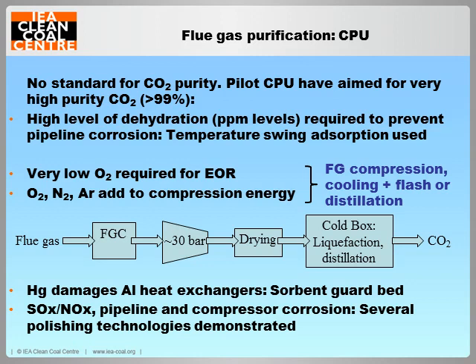Even though oxy-fuel flue gases are enriched in CO2, contamination due to air ingress, residual oxygen and conventional flue gas contaminants means that a fairly elaborate purification process is still required to produce a CO2 stream fit for sequestration. While deep dehydration to PPM levels of water is required to prevent pipeline corrosion, it is also energetically favourable to remove nitrogen and oxygen rather than compressing them to pipeline pressure with the CO2. The cryogenic condensation necessary for removal of these light gases uses sensitive compressor and heat exchange equipment, which imposes its own purity requirements, including almost complete removal of SOx, NOx and mercury.